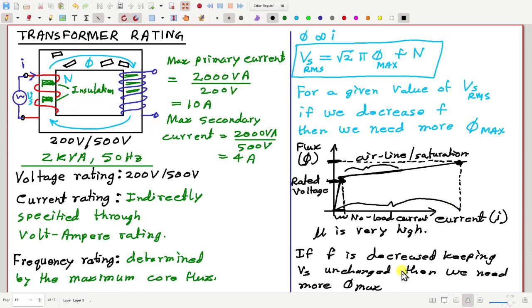Therefore, we should not operate a transformer at a frequency lower than the rated frequency, because then we need a very high no load current, which may cause damage. Even if it doesn't cause damage, the assumption that for a good ideal transformer the no load current should be very small, close to zero, is violated. So that's a problem. Okay.